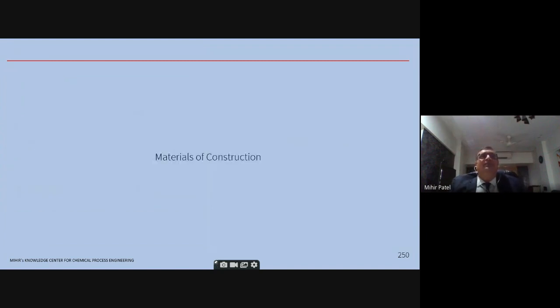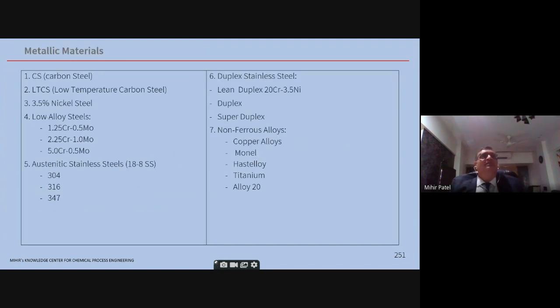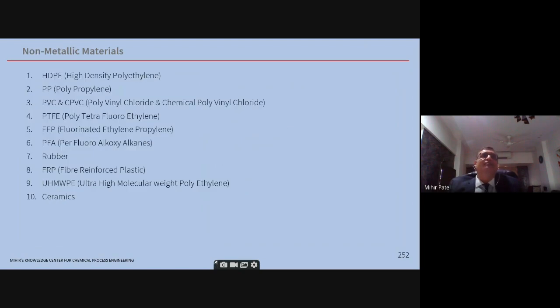Material of construction. Now, briefly, I'm going to cover here the different metallic materials available. Carbon steel, LTCS, low alloy steels, austenitic SS, which is 304, 316, duplex SS, which is used, let's say, in seawater service, super duplex is used, non-ferrous alloys are there. So again, the metallurgical engineer will choose this. The process engineer is also heavily involved in telling the metallurgical engineer what the compositions of the streams are, so that a proper choice can be made.